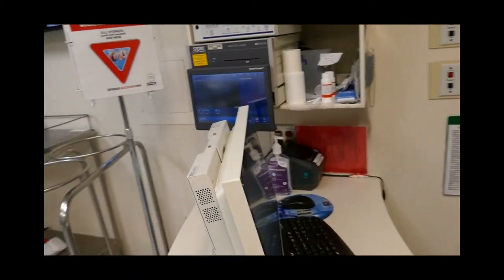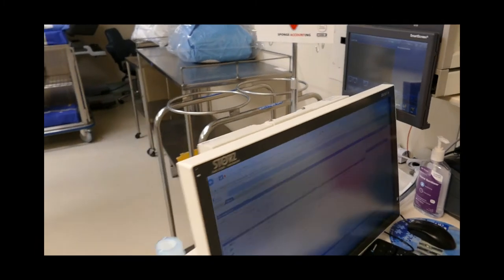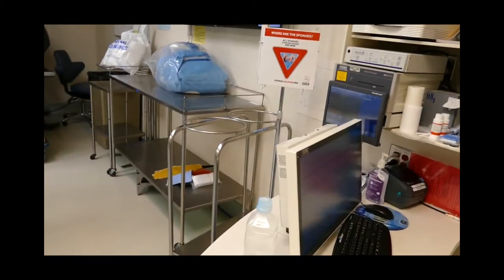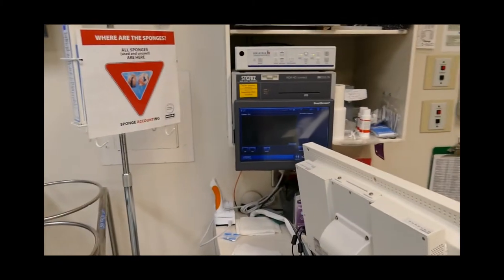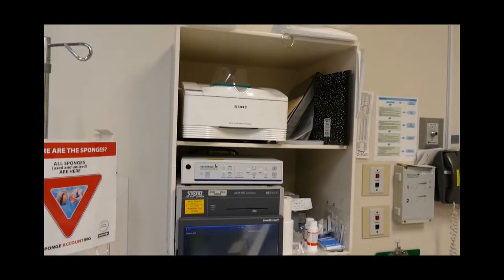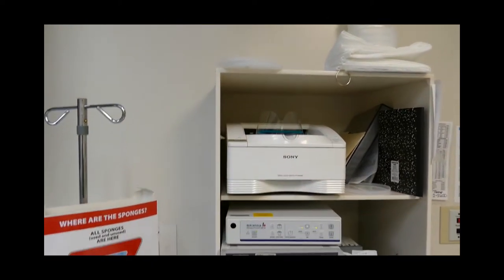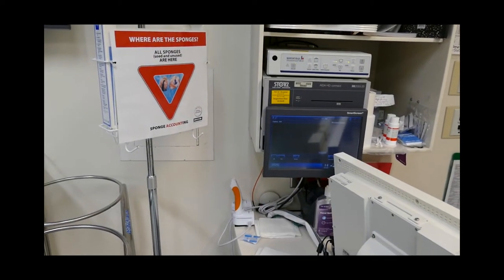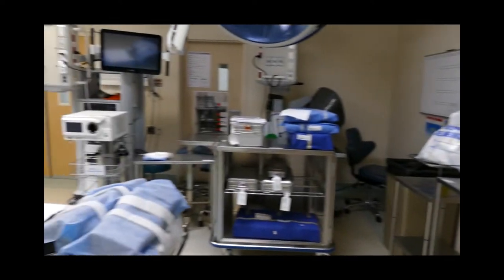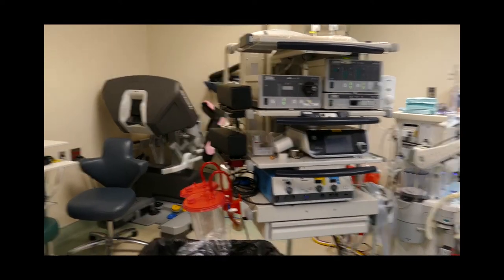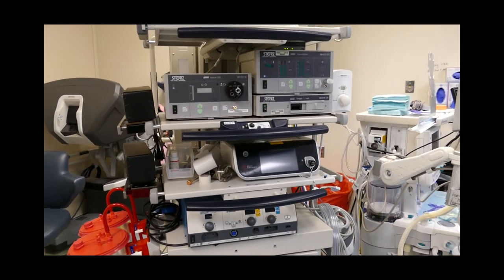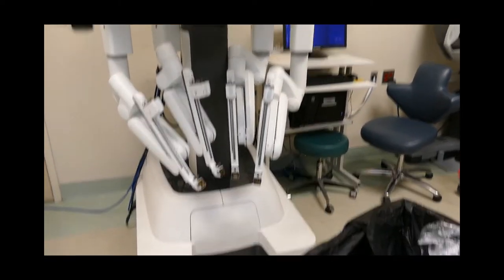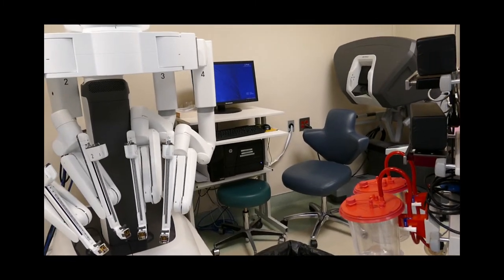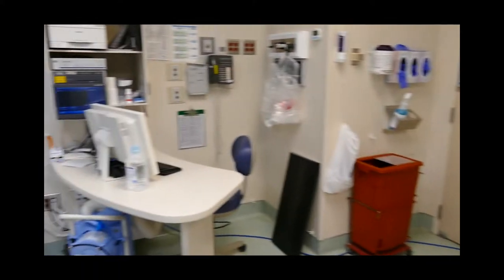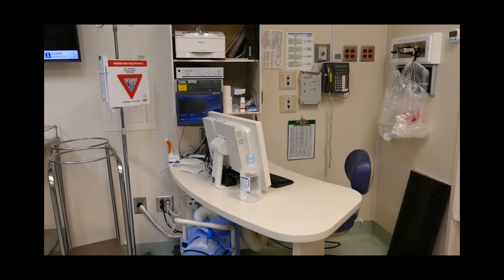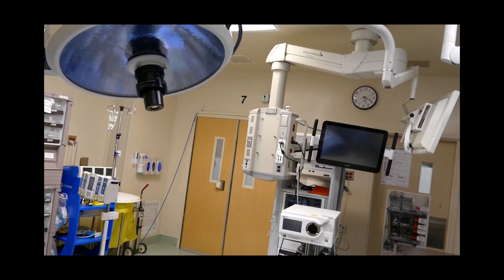Coming over here, this is the touch panel, the circulator system. Oh, actually, look at that. Lovely. They're still logged in. That's a big no-no. Video recorder, camera controller for the in-light camera, and the printer so that they can print images of whatever they're capturing. Now, this system here integrates the camera over here, the inputs from the Da Vinci robot, and we have the surgeon's computer over there. The nurse's computer is another input, and there's actually a series of inputs over here on that boom.